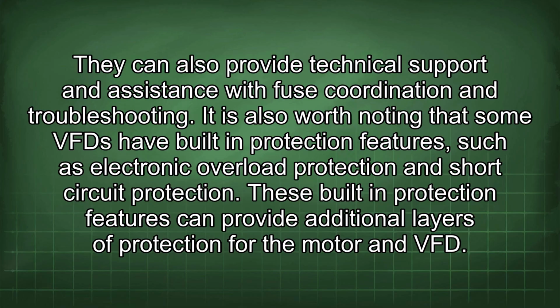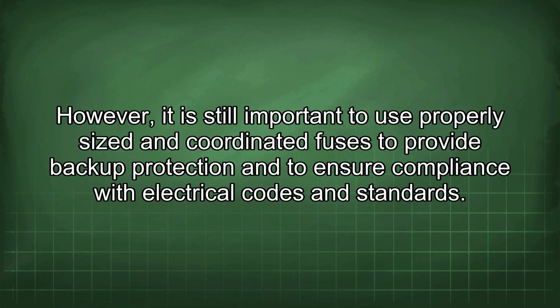It is also worth noting that some VFDs have built-in protection features, such as electronic overload protection and short-circuit protection. These built-in protection features can provide additional layers of protection for the motor and VFD. However, it is still important to use properly sized and coordinated fuses to provide backup protection and to ensure compliance with electrical codes and standards.